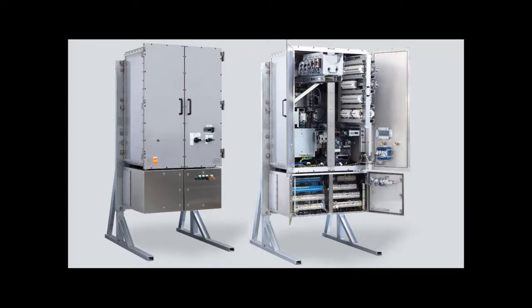So how do you visually inspect an EXD box? Unless you have an inspection window, you perhaps will not be seeing the damage that has happened inside. With this type of installation, anybody walking by can see the rupture disc has blown out. So it's a great visual indication. It actually reduces your inspection costs, because during a visual inspection, you can see that an explosion has happened. So that perhaps can give you an indication that things are overheating, things are arcing and sparking.